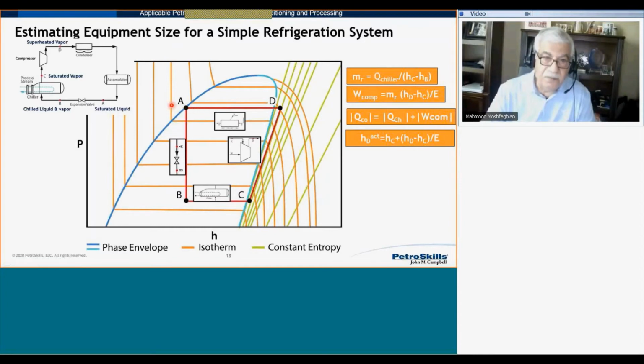So if I extend this, this is my condenser temperature. Suppose this is 104 degrees Fahrenheit. And I can read the pressure on the y-axis, which is about 200 psi. Of course, the P-h diagram I'm going to use for calculation has all the actual numbers on both axes and on temperatures as well.